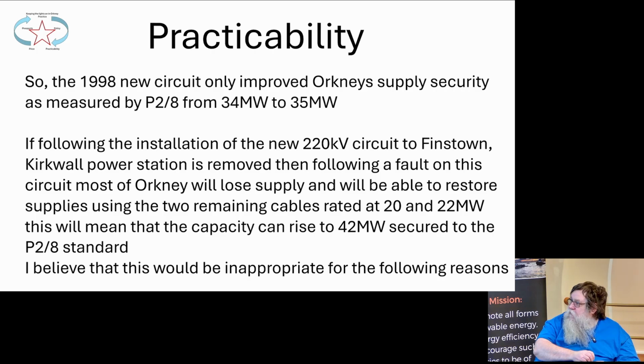So following the installation of a new 220 kV circuit to Finstown, is everybody aware that we're getting a new 220 kV circuit to Finstown? Anybody that's a surprise to? Nope. Right. So there's two options. Kirkwall Power Station could be removed. Then following a fault on the circuit, most of Orkney will lose supply and we'll be able to restore supplies using the two remaining cables rated at 20 and 22 megawatts. The secured capacity can rise to 42 megawatts from 35.